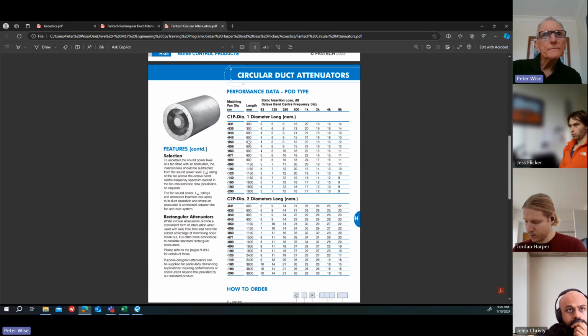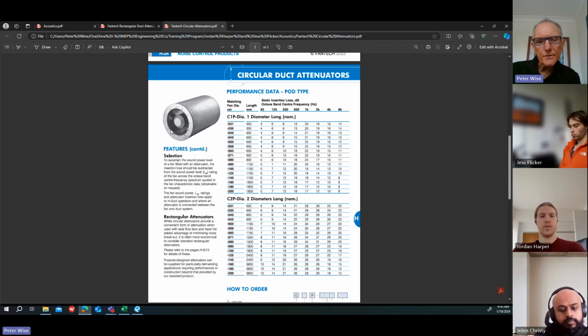When you go to a pod, these give improved attenuation, but you need to have a duct piece between the fan and the attenuator, particularly on the inlet side to the fan, because the pod will cause turbulence in the airflow, which will affect the fan performance. So you need to have a spacer piece, say 1 metre long of ductwork between the attenuator and the fan if you use this type of attenuator.